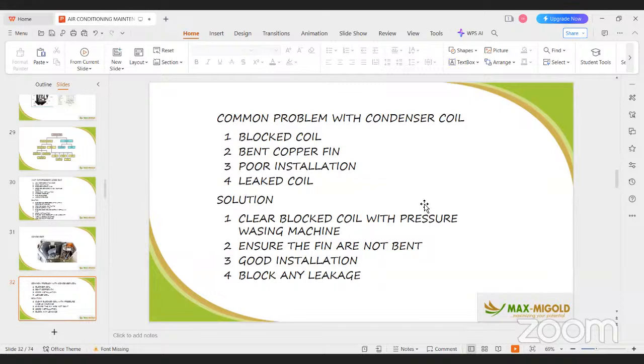How do you identify it? There is gas testing equipment for refrigerant, and there is a cheaper form which uses what? Soap water. Buy a detergent soap with water and mix it together till it forms a lather. Put the lather around your pipes. Anywhere you see bubbles coming out, you know there's a leakage at that particular point. And if you must braze, you must pump down. Don't braze while the refrigerant is still in the pipe. Some of the refrigerant can actually turn into a bomb.